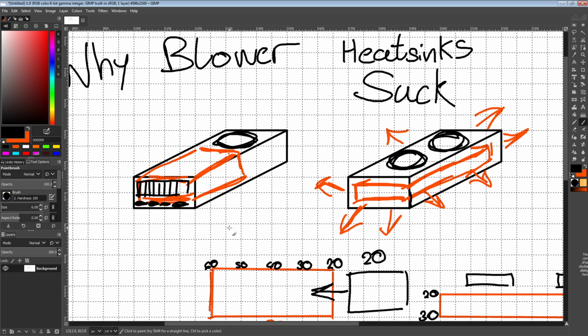You want actual turbulence in the air, because if you just shove air in sideways with really clean airflow, you end up with a layer of air right against the fins that isn't really moving and is close to the fin temperature, while the air actually flowing through the heatsink doesn't really contact the fins. That's where you get fancy non-straight fin geometries on a lot of heatsinks — '3D fins for better thermal transfer' — that's where that comes from.